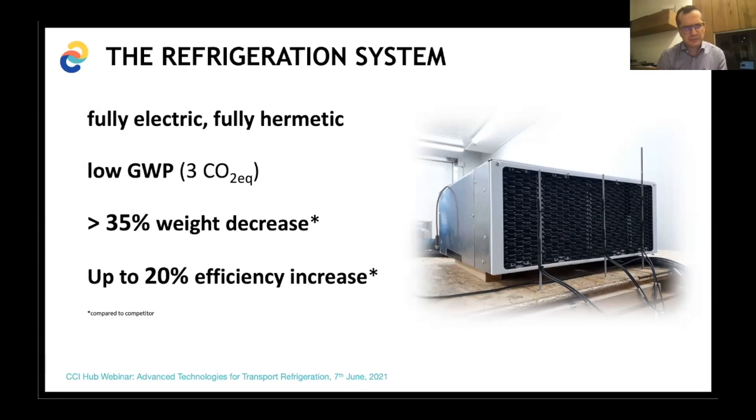As I mentioned before, one aspect that I didn't mention, and it's really important since that question came out also in the Q&A session and from the panel, is propane due to its refrigerant properties. It's not a miracle, it's not black magic, it's just because of the thermodynamical properties. It can be operated at high temperature without any decrease of capacity. You can see that just in the pH diagram, where the critical temperature is really high up there. And this is a huge benefit, of course, compared to other refrigerants where you have oil issues and also you don't have any heat exchange area in the two phase of the pH diagram or TS diagram. And this is quite a huge benefit also for other applications than refrigeration.